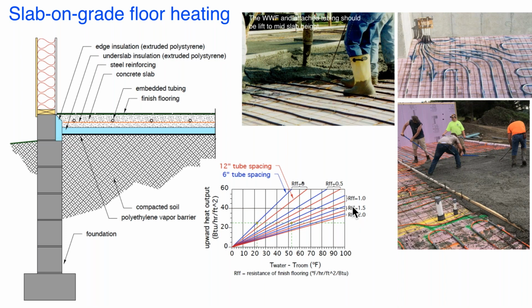And then these different lines, RFF just stands for finished floor resistance. If it's a bare slab, RFF equals 0. If you're putting a ceramic tile over it, probably somewhere around 1. If you're putting a commercial carpet and you're gluing it to the slab without any kind of pad under it, you're probably going to be about 1.5 to possibly 2. And you'll see that makes quite a difference in terms of the water temperature that you will need above the room air temperature for a certain rate of heat output. And the other thing you can see here, these lines are plotted for both 6-inch tube spacing and 12-inch tube spacing. The closer you bring the tubing, the better the heat exchanger that floor is. So trade-offs there. But again, this is a nice low temperature option.